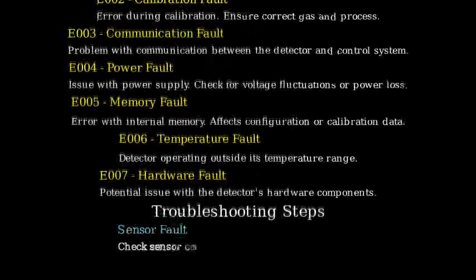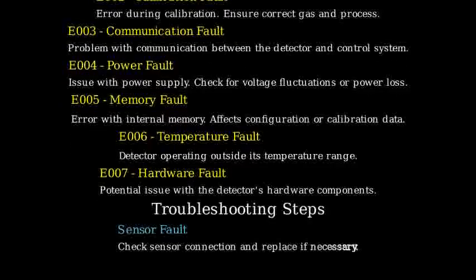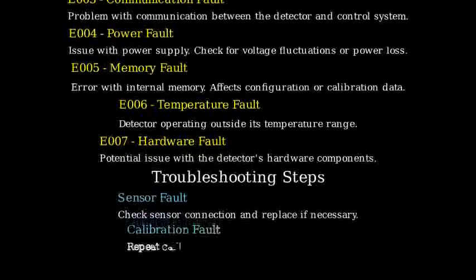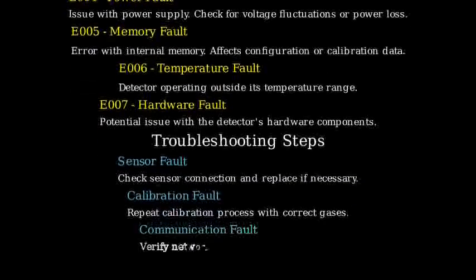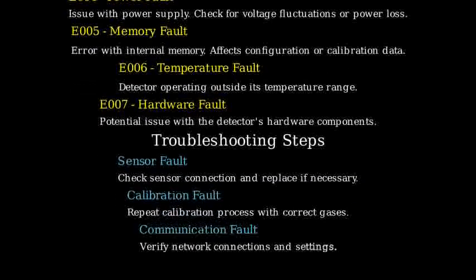For a sensor fault, check the sensor connection and replace if necessary. For a calibration fault, repeat the calibration process with correct gases. For a communication fault, verify network connections and settings.